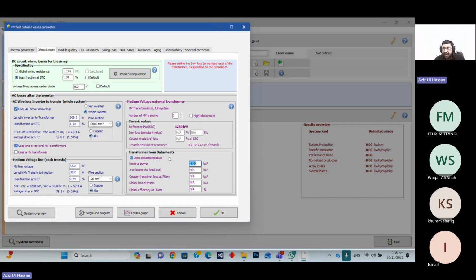So, as per the vendor data, mostly we get that data for each transformer, how many iron losses and how many copper losses are available in your transformer. But as per the experience-based system, we have 0.1% loss in the iron phase and 1% in the copper phase, in the aluminum winding transformer. For the copper winding transformer, the losses are less than that. So you have to check with the transformer vendors.